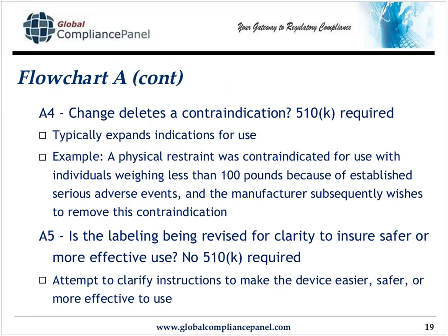A4 says, is my labeling changed? Am I deleting a contraindication? If the answer is yes, I must submit a new 510K, because when you delete a contraindication, as opposed to adding one, you're typically expanding the indications for use. An example is there's a physical restraint. And previously, it was contraindicated for use with individuals who weighed less than 100 pounds. But now I want to remove this contraindication.